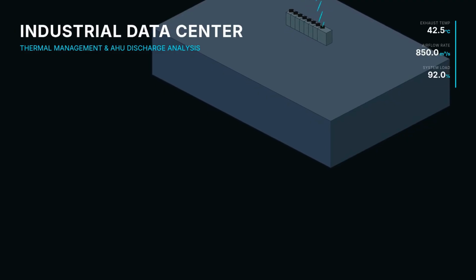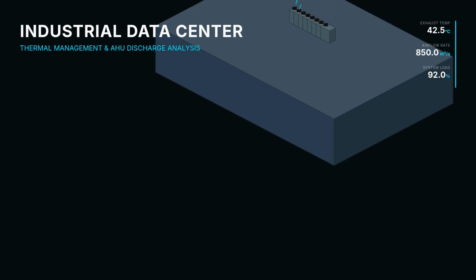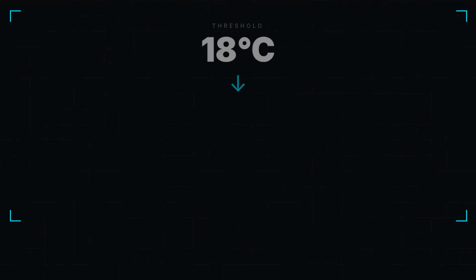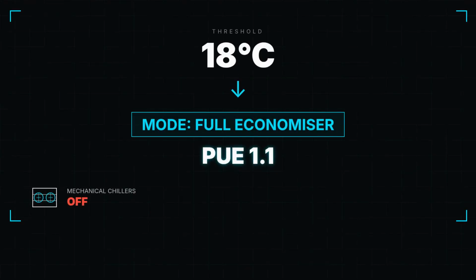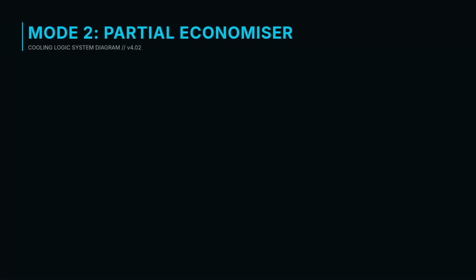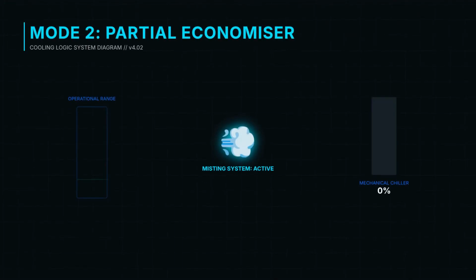Hot return air is discharged well above the intake level, creating a physical barrier to prevent thermal recirculation and efficiency loss. When outdoor temperatures are below 18 degrees Celsius, we operate in full economizer mode. The mechanical chillers are completely powered down, and our instantaneous PUE approaches a remarkable 1.1. Between 18 and 28 degrees, we move into partial economizer mode. Adiabatic pre-cooling brings the supply air within range, while mechanical chillers are only partially loaded to bridge the thermal gap.